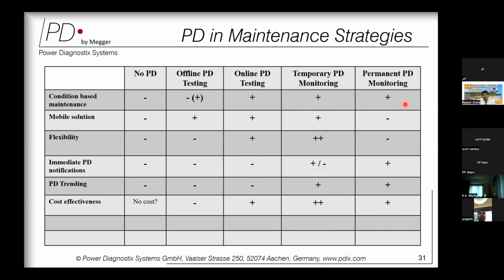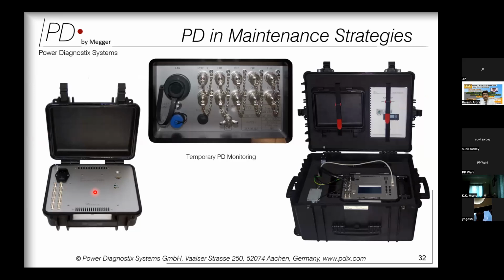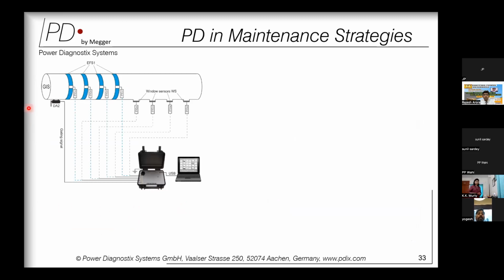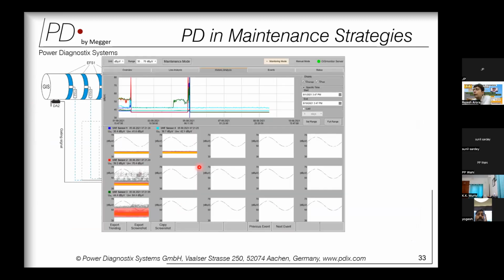So let's see in the next slide what this solution is. We have a portable instrument. It can be connected using a casing, which can be used if you want to leave this instrument for monitoring outside of the switchyard. Otherwise, you can connect the same instrument for temporary monitoring. The setup is like this: you have this GIS, you connect all measurement channels to your portable instrument, and the portable instrument is connected to software. Our portable instruments are equipped with software which is 100% the same as what we provide in a permanent monitoring system.